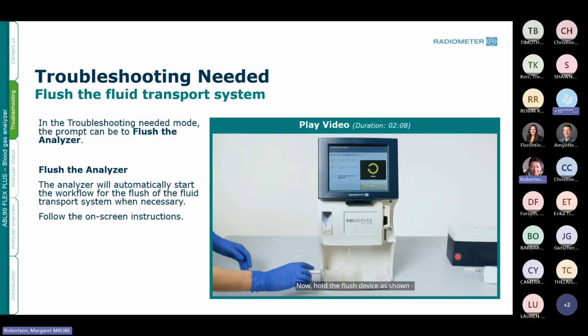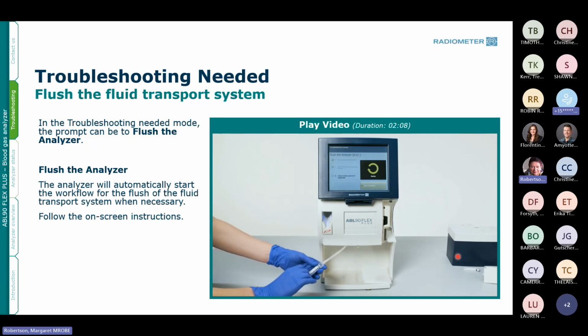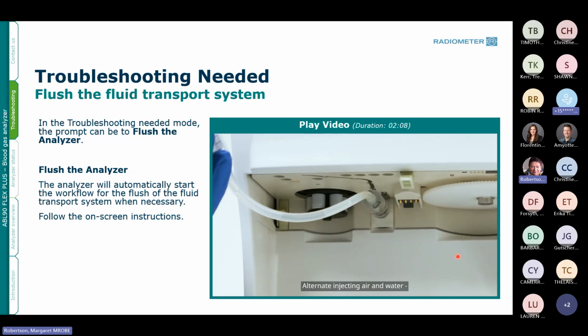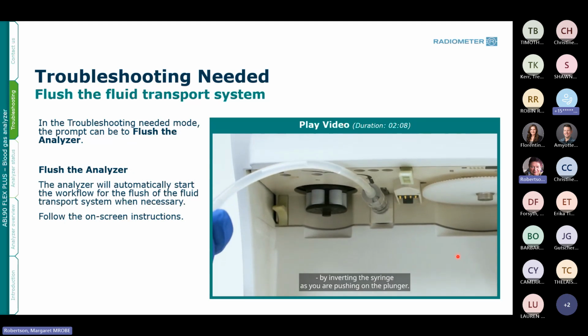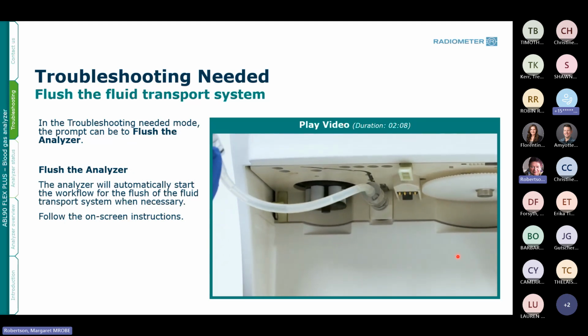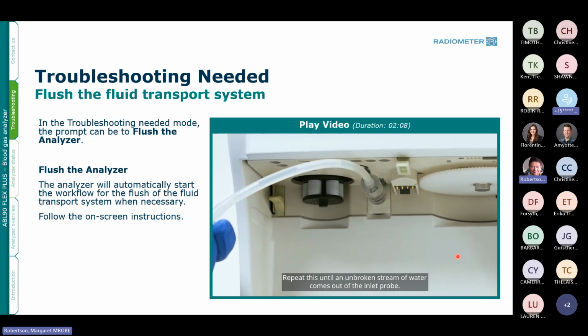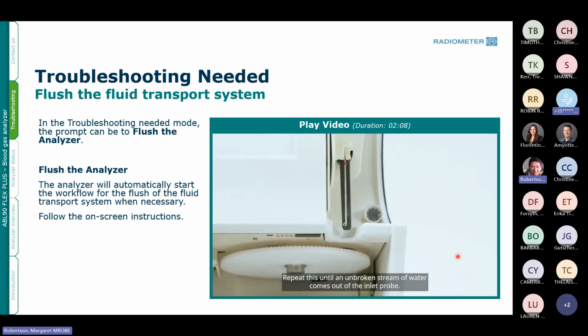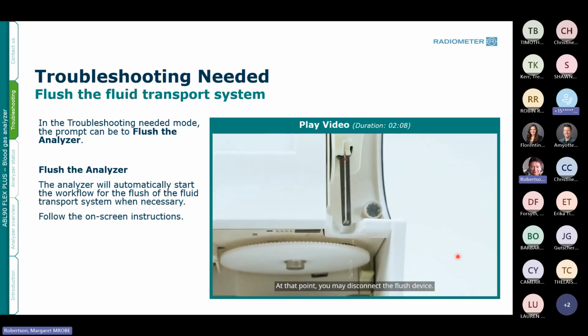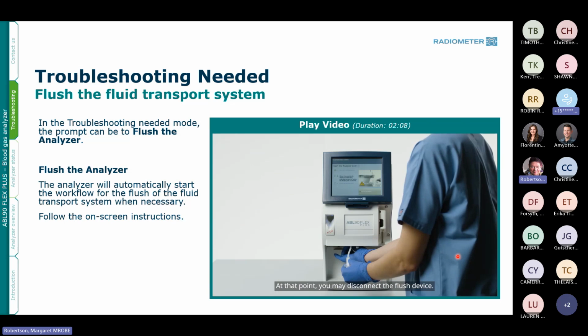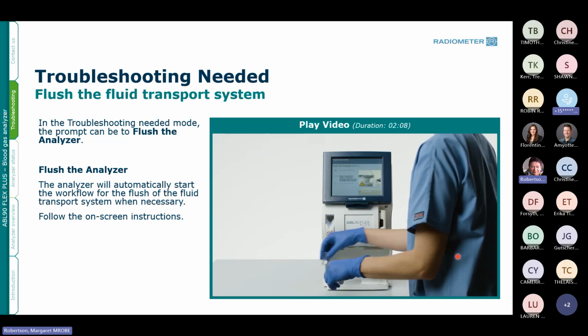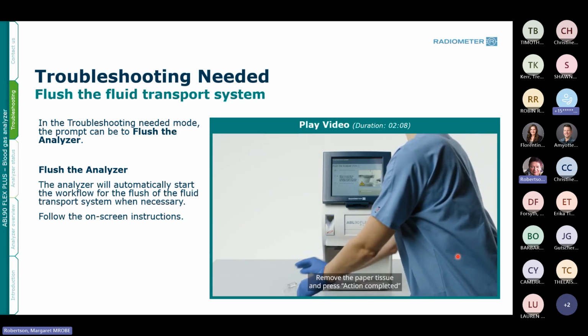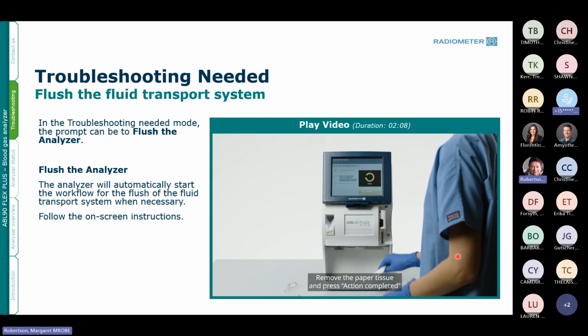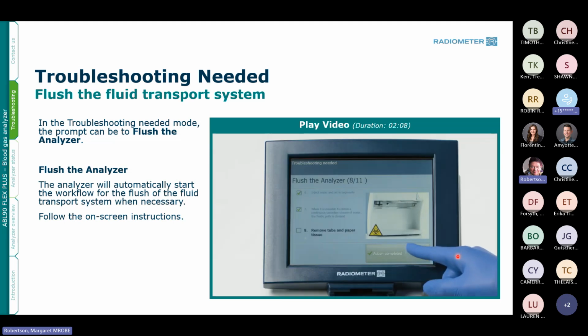Now hold the flush device as shown to inject air and water into the analyzer. Alternate injecting air and water by inverting the syringe as you are pushing on the plunger. Repeat this until an unbroken stream of water comes out of the inlet probe. At that point, you may disconnect the flush device. Remove the paper tissue and press Action Completed.